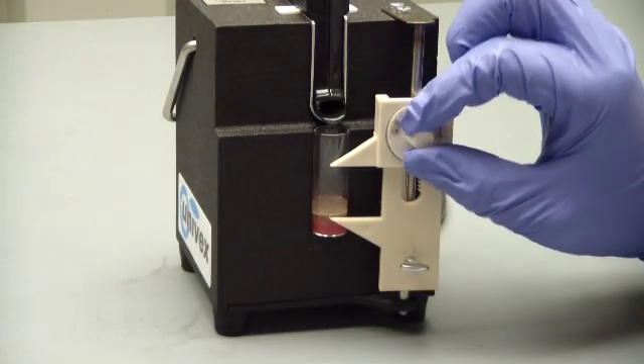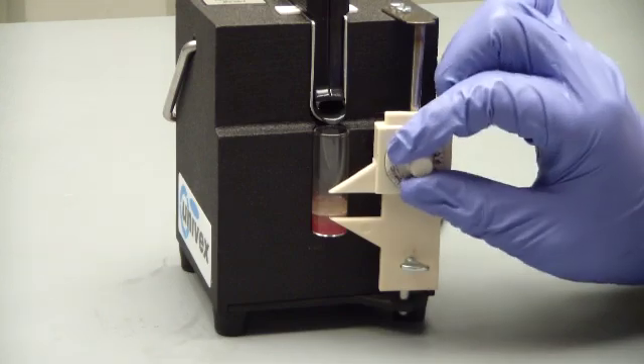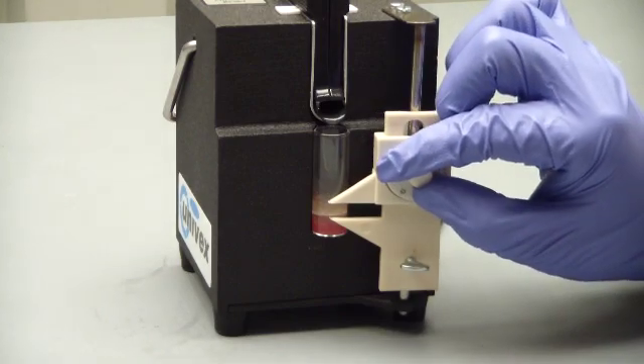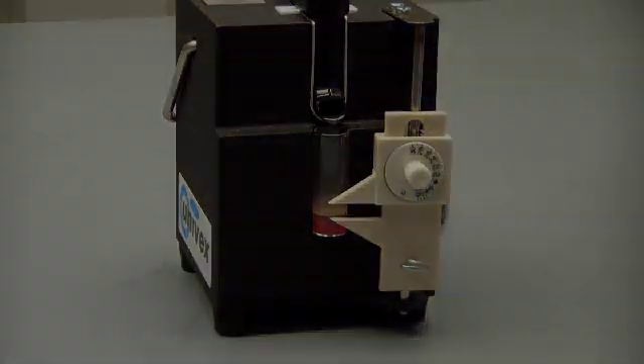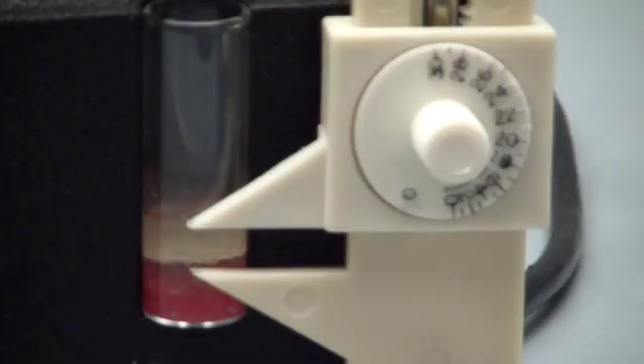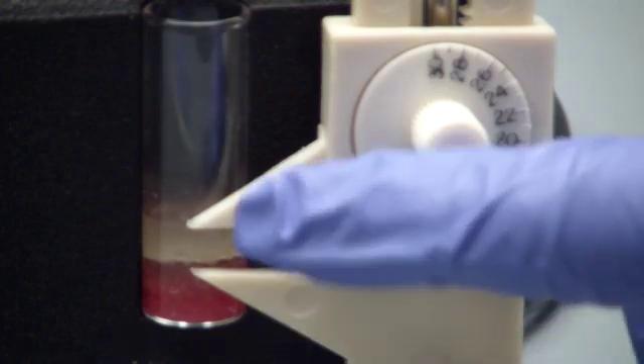Now using the dial, lower the upper jaw to the top of the liquid. To ensure accuracy, make sure you are at eye level when setting the upper and lower jaw.